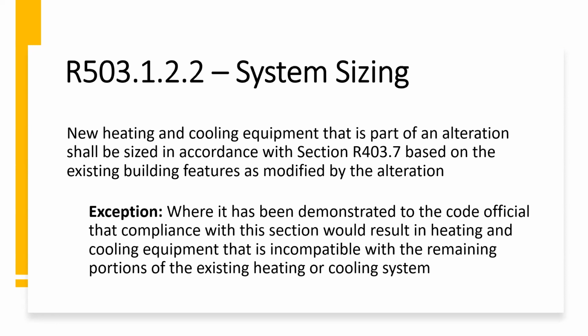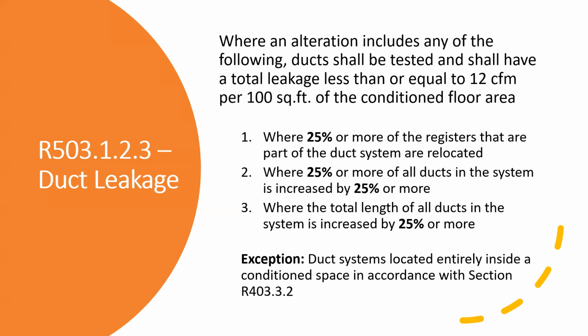Now it's brought into the existing buildings, and it says any new heating and cooling equipment as part of the alteration shall be sized in accordance with that same section, which talks about Manual J, Manual S being done for that. So if you have alterations, additions being done, the alterations, especially if they're replacing the equipment, need to have that. Of course, it says where it's demonstrated by the code official that compliance with this section would result in heating and cooling equipment that is incompatible. In other words, if something is inaccessible, but you're replacing the other that is accessible, they should not be made to have to all match up and meet that new requirement. So you have to look at part of it, if it's all acceptable, if you can reach some of that and it's accessible.